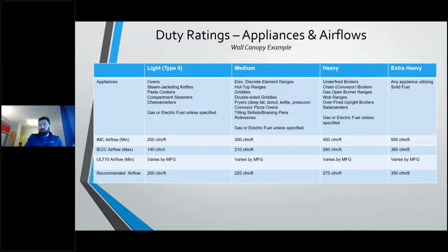So we now have our capacity of our CFM. In most instances, your supply CFM is going to be correlated to your exhaust CFM. So if you're using a dedicated makeup air system, best practice is to have 80% of your exhaust air be supplied by your dedicated makeup air system.